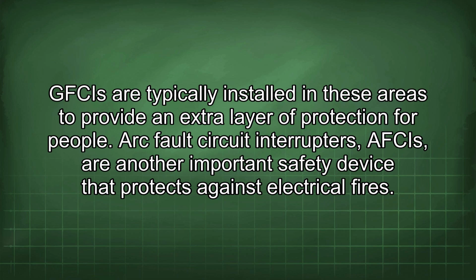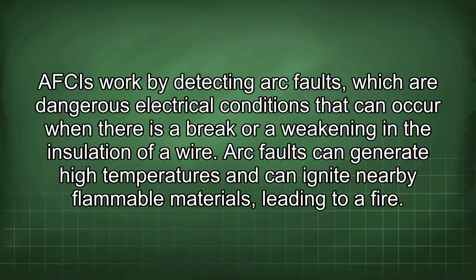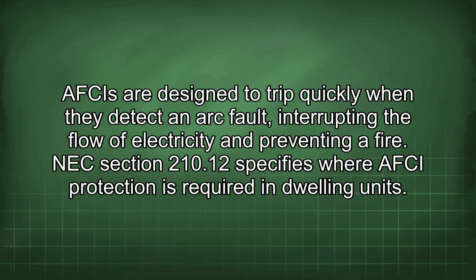Arc fault circuit interrupters, AFCIs, are another important safety device that protects against electrical fires. AFCIs work by detecting arc faults, which are dangerous electrical conditions that can occur when there is a break or a weakening in the insulation of a wire. Arc faults can generate high temperatures and can ignite nearby flammable materials, leading to a fire. AFCIs are designed to trip quickly when they detect an arc fault, interrupting the flow of electricity and preventing a fire. NEC Section 210.12 specifies where AFCI protection is required in dwelling units.